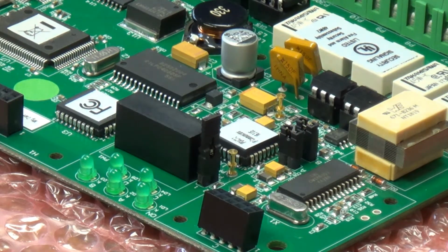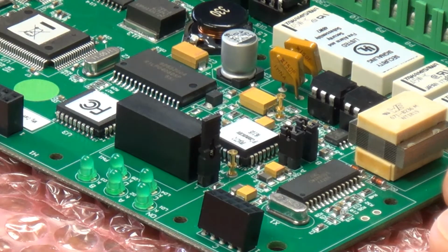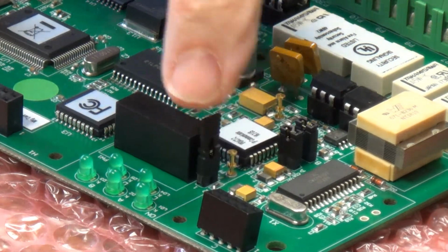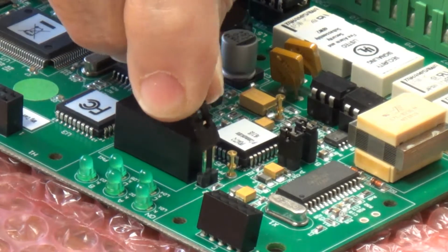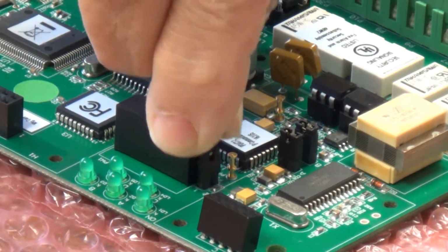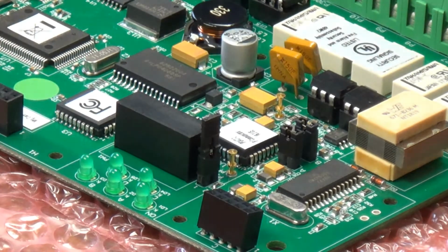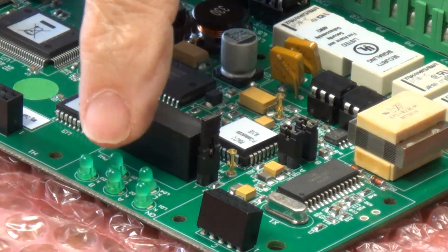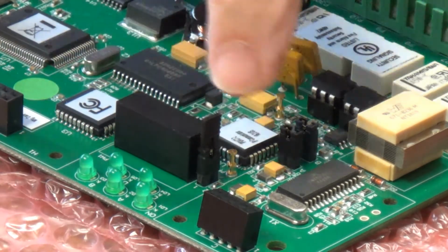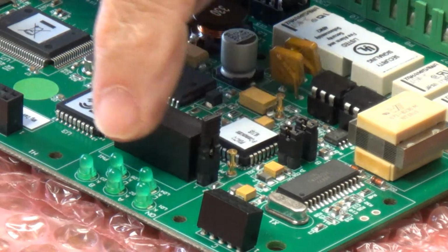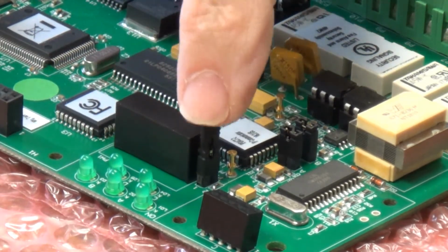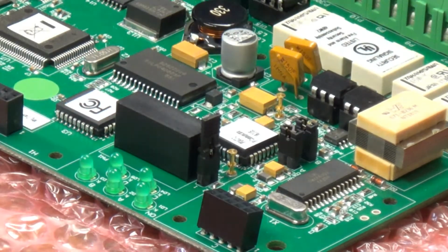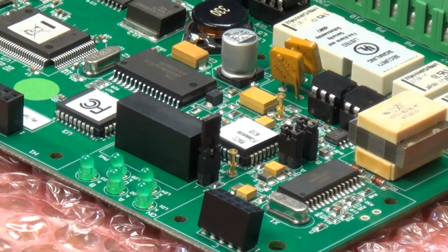Okay, I'm going to demonstrate resetting the IPDACT card back to its default. First thing I'm going to do is take this little jumper and short the two leads together. Now when I apply power, these lights here are going to go around once, they're going to go around twice, and right after they go around twice, I'm going to pull this jumper and they're going to go around one more time, and then it'll be set to default. Here we go.